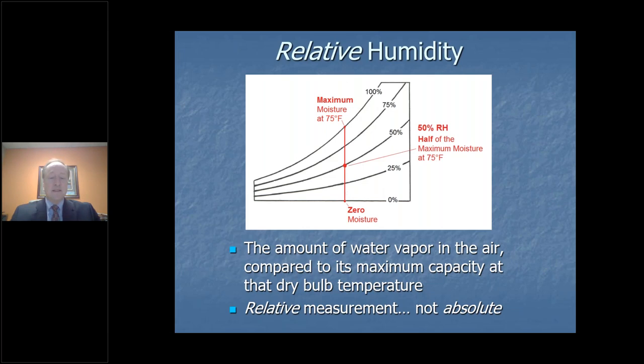Now what that means is relative to that particular temperature, let's say you would take a cubic foot of air, it is holding 50% of the moisture that it could hold until it was completely saturated. So this distance here is the same as this distance here. But if you change the temperature and you don't remove moisture, then you would increase or decrease the relative humidity. So we always need to understand that when we refer to a relative humidity term, we have to also account for what dry bulb temperature that relative humidity was read.